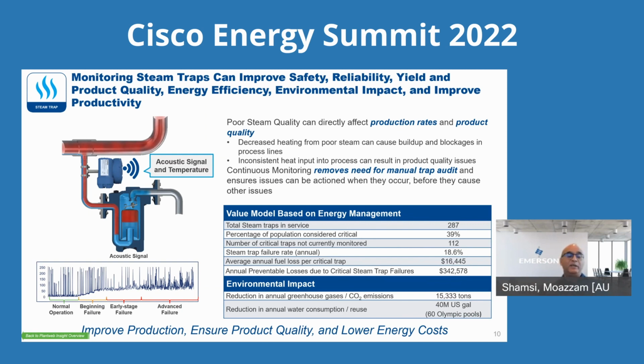That steam is used for many different things, but what you want is to ensure your steam traps eliminate condensate from the lines. We can tell whether a steam trap is bubbling or has gone abnormal through the use of an acoustic sensor attached to the trap. That tells us whether the trap's in normal operation or whether there's potential for it to fail - giving advanced notification of impending failure. That means we can get somebody out there to investigate and intervene ahead of time, using that enabling infrastructure - perhaps used for mobile workers - but also enabling this acoustic sensor, clamped onto the steam trap, to get that data.